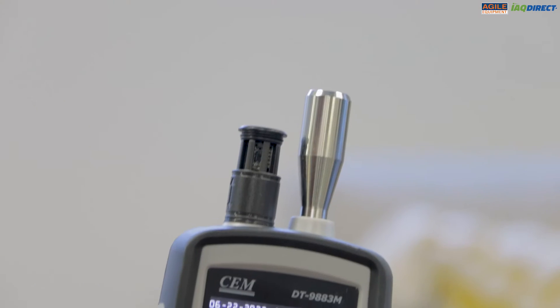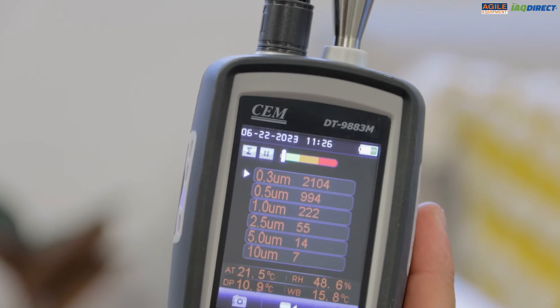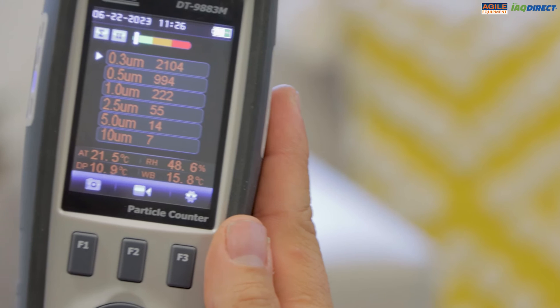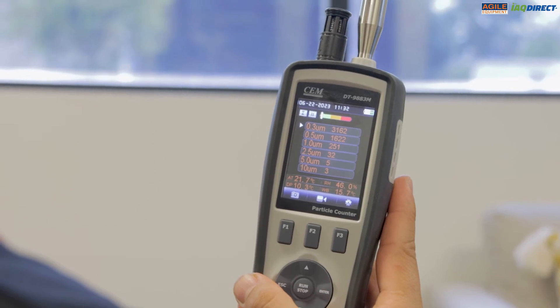By default, the sampling time is set to 21 seconds. This is the time it takes to sample 1 litre, and therefore it is 2.83 litres per minute. If the sampling time is not long enough, you can change it in the settings.